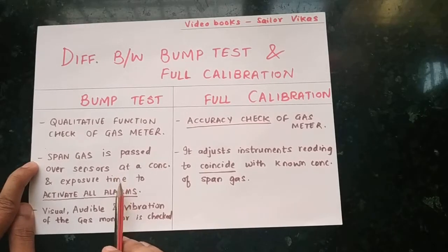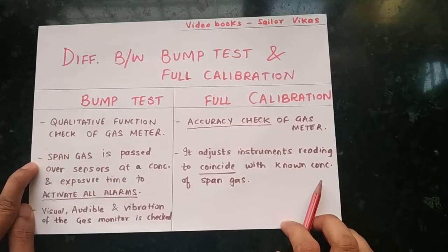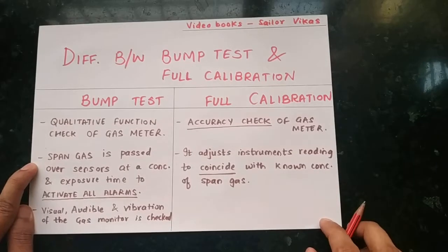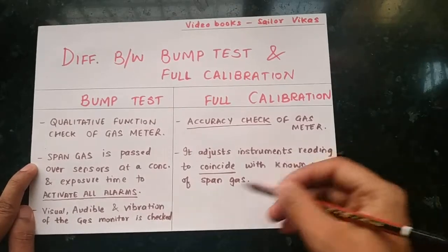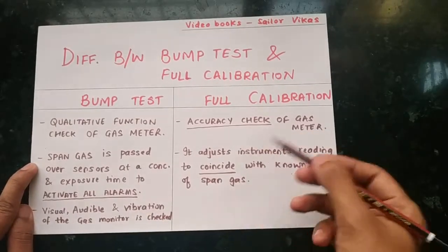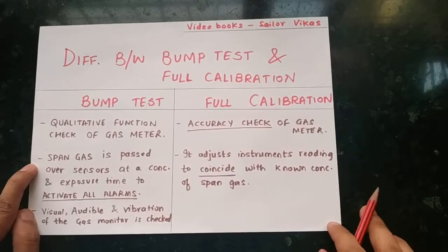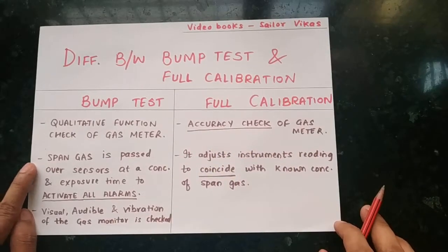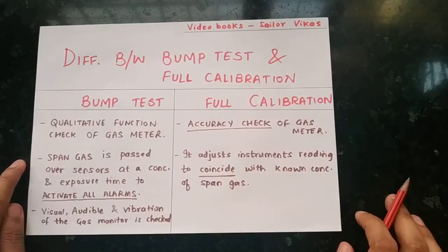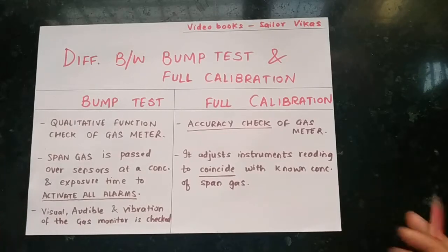In bump test, visual, audible, and vibration alarms of the gas meter are checked. In full calibration, there is no checking of alarms — it is just adjusting the value of the gas reading and carrying out an accuracy check. That is all about bump test and full calibration. Thanks for watching.